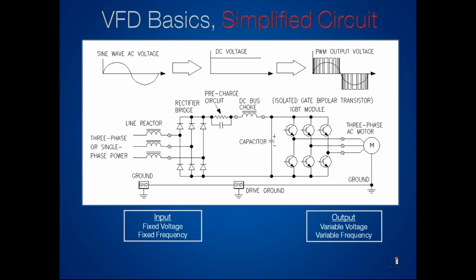So basically what we've got going on here is we've got our AC power coming in, it's being converted to DC, and then that DC is being pulsed out to our motor. The motor is an AC motor, right? So essentially what's happening with that pulse width modulation is we're tricking our motor into thinking that it's receiving AC voltage, okay? It's receiving DC, but that pulse width modulation is making the motor think that it's AC voltage, okay? If you guys have any questions about that, definitely raise your hand and we can address those later. So input, you've got your fixed voltage, fixed frequency. On the output side of things, variable voltage, variable frequency, all based on how fast we want to run that motor, okay? Next slide, please.